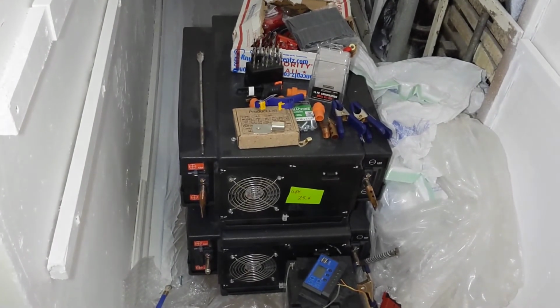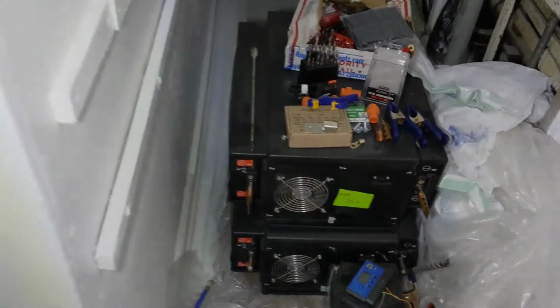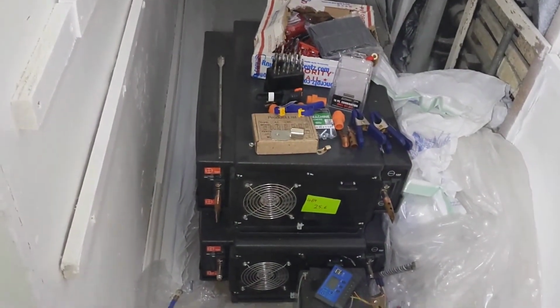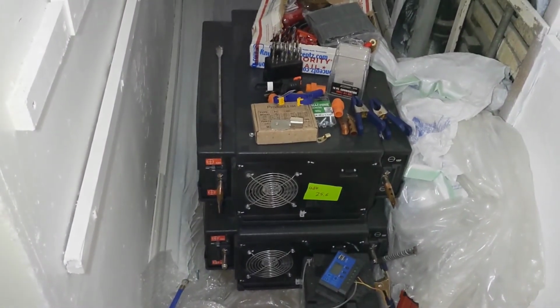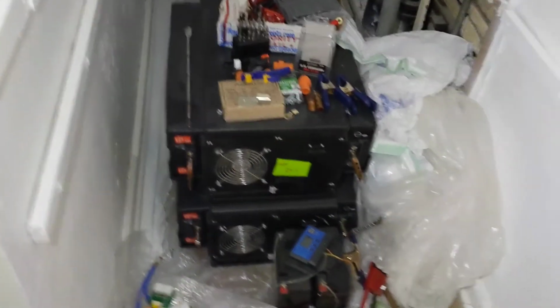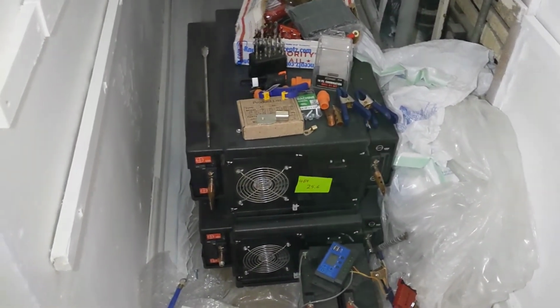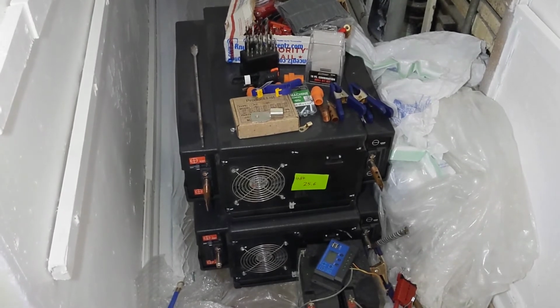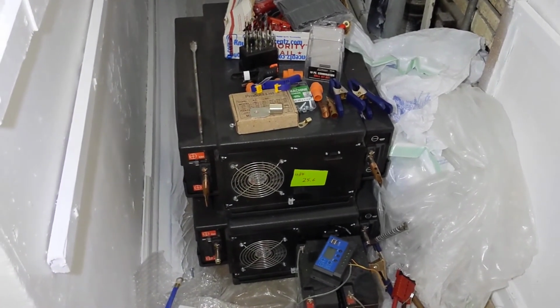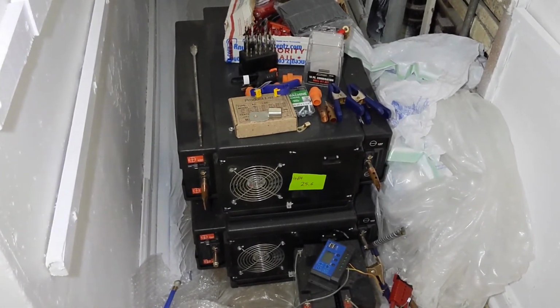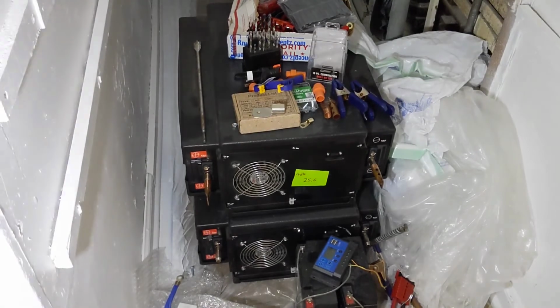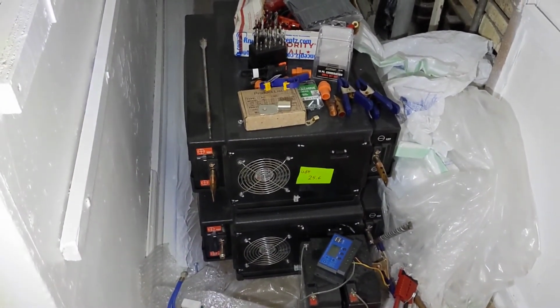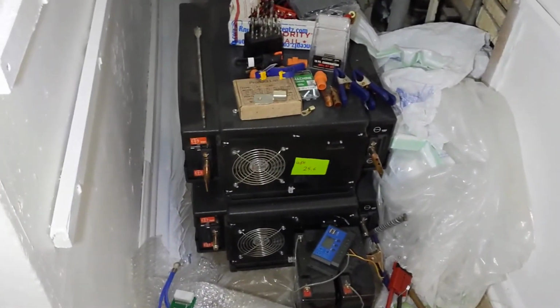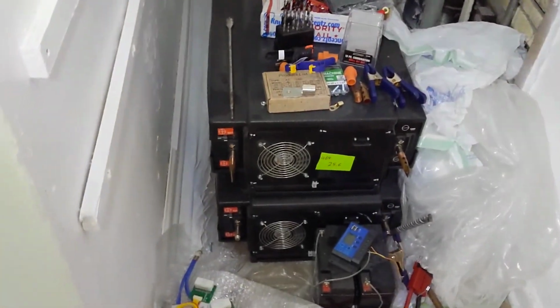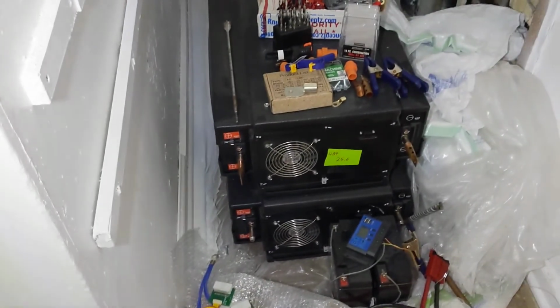I do wish that when you set the charge current, which is what's actually going back to the batteries here, that maximum charge current was handled as a true maximum. What I mean by that is, when you set 60 amps as the maximum charge current, it's going to charge at 60 amps. It's not variable. It will charge at 60 amps independent of what your other AC loads are coming out of your generator, and it can very easily overrun the one leg of the generator that you're running. I had that problem a lot. It was kicking in and out, instead of running off the generator, because the generator just couldn't support that much load off one leg. So it would kick over to battery power, which meant my generator was running for no reason.